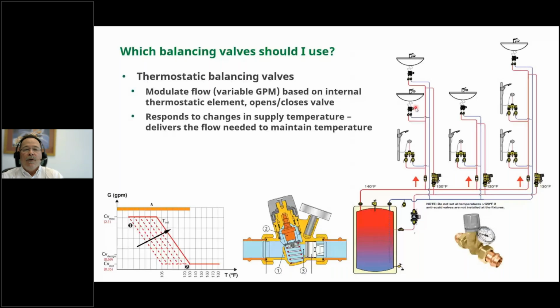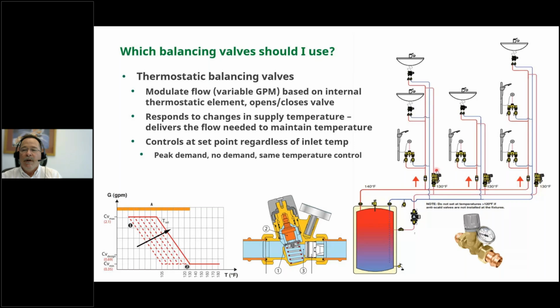So they control their set point regardless of inlet temperature. Right, so if you have this one set, for example, at 130 degrees Fahrenheit, it will open and close to try to maintain 130. If the temperature drops, it'll open up, bringing more water from the supply trunk into this group of fixtures to try and get to 130. The same thing will happen way out here at the end. The water coming into this riser probably is not going to be the same temperature as the water coming into this riser that's really close to the heat source, right? It's going to be less, but that doesn't matter because the valve will still control at 130 degrees Fahrenheit.